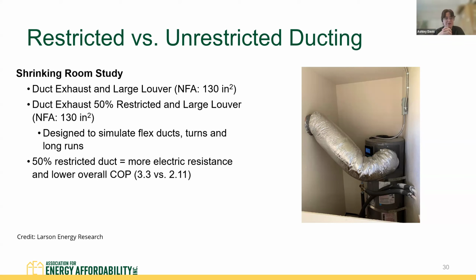So they did a couple different configurations with ducted exhaust and then louvers for the intake. And they found that when they restricted the duct by about 50%, which was designed to simulate kind of a bent, restricted, crunched flex duct, that it led to a pretty significant drop in COP because there was a lot more electric resistance usage, because that internal fan could not overcome the pressure of a restricted duct. So if you're going to duct, make sure you do it correctly and that your ducts are as unrestricted as possible. Next slide.